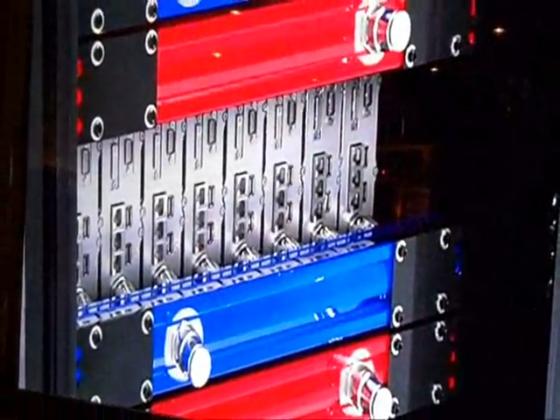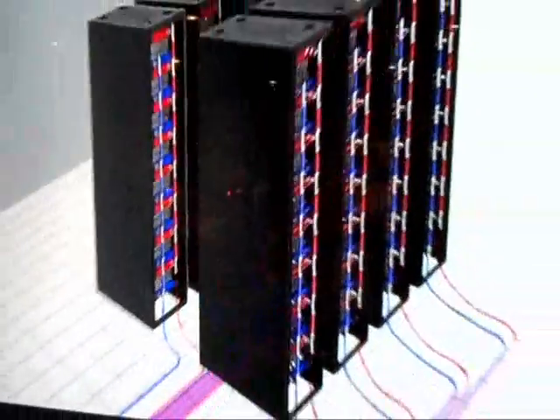You'll see there's the inside of it and a schematic showing that the cooler fluid goes in — again, this is dielectric fluid completely protecting the inside of the equipment, no contaminants — keeping everything at a nice 75 to 80 degrees. The hot fluid comes out through extruded aluminum. We're not worried about sand, dust, air, or contaminants of any kind, so we can sell these individually into caustic, hazardous, and harsh environments. When selling into data centers, we simply manifold the back really nicely and easily, and there's not a single fan in that entire unit.